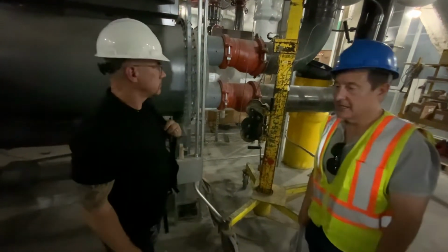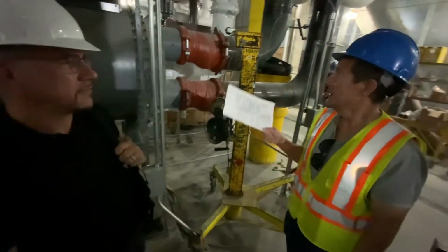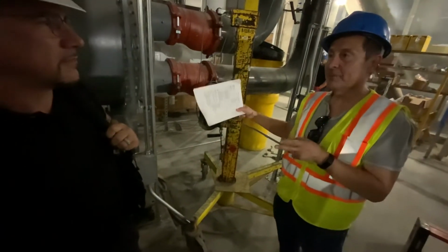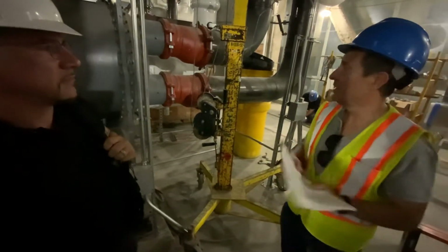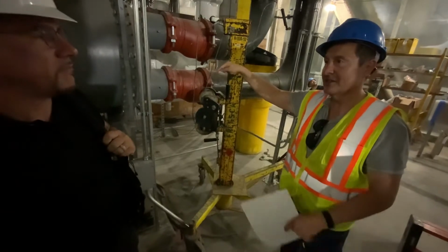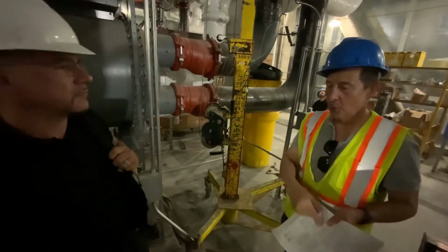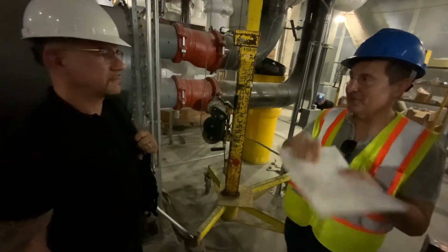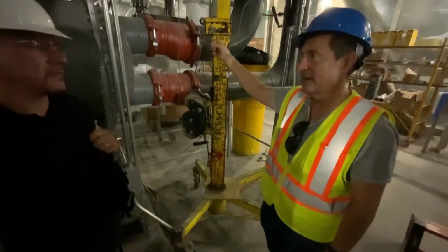Yes, correct. And I'm not sure they're going to do it this way, but they should. When they go from one stage to the next, if they have one machine running and they're ready to start a second machine, the best way to do that is to demand limit or unload the first machine to 50% first. Open up the other valve and then start the second machine. Once that machine's gotten up to 50%, it'll load up. Then release the force on the first machine.